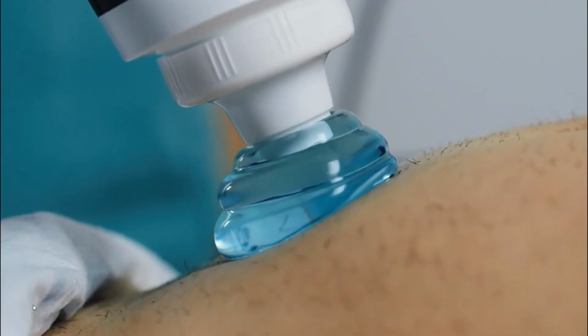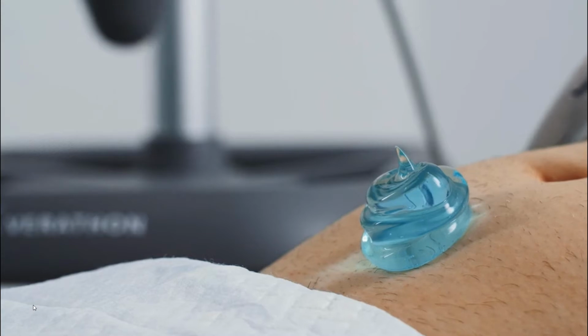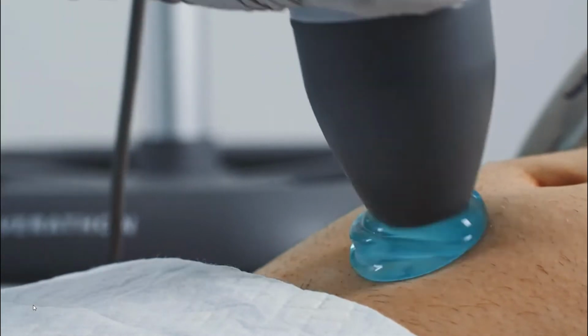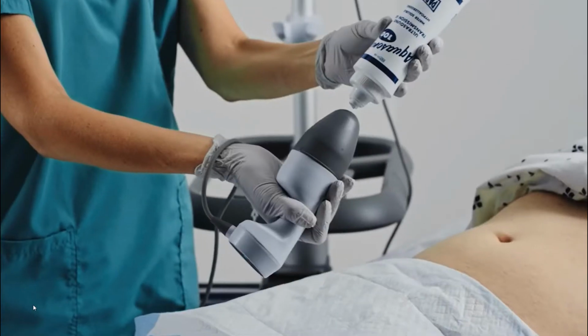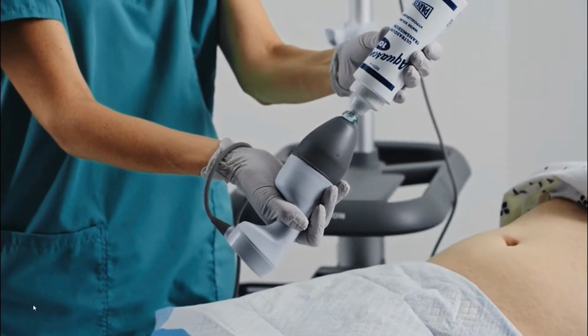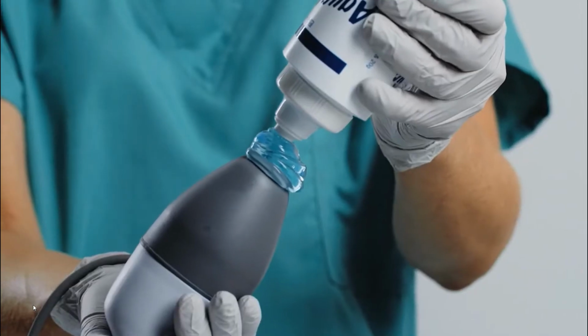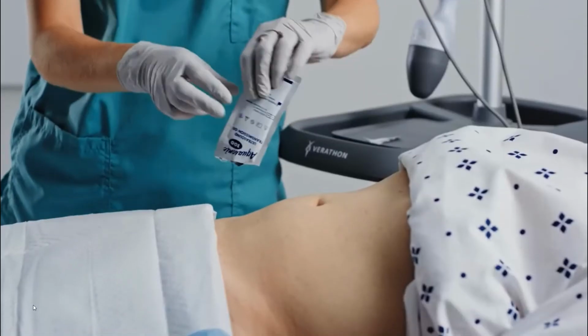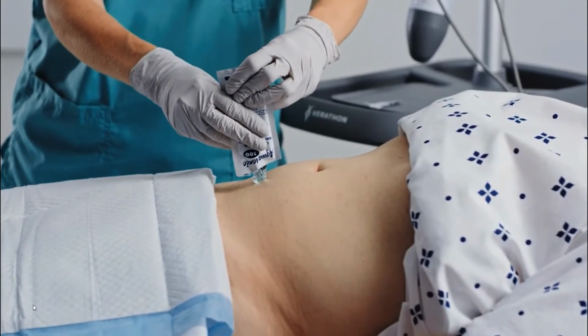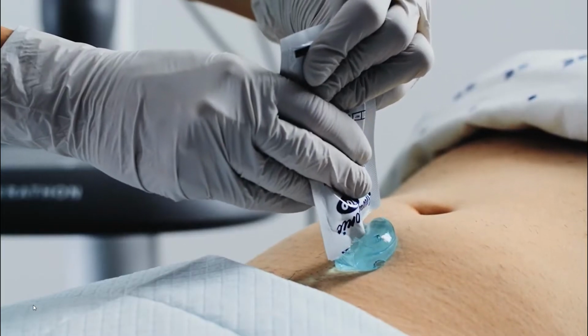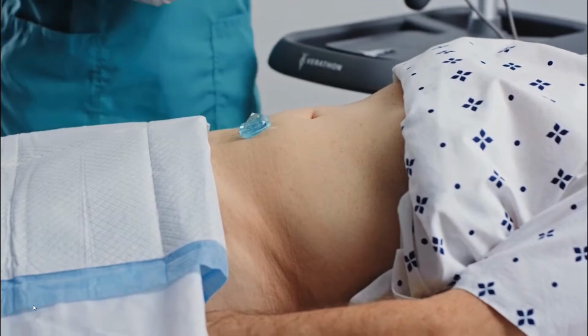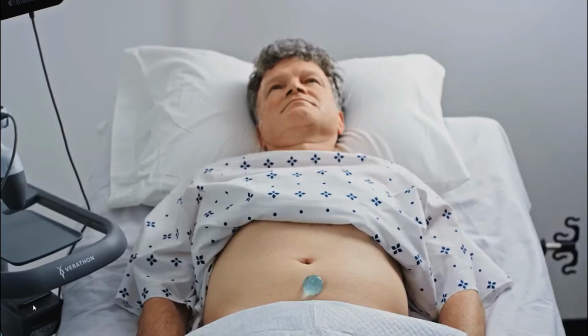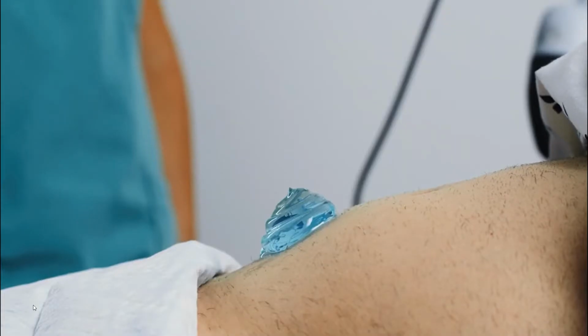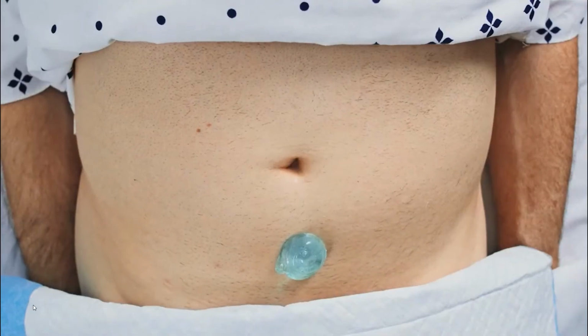Ultrasound waves have a difficult time traveling through air. With medical devices, a thick ultrasound gel is used to reduce air gaps between the patient's skin and the ultrasound probe. It is important to use an ample amount of gel between the skin and the probe tip. Apply gel to the probe tip or abdomen. A single-use 20-gram packet provides ample gel for use with most patients. After the gel is applied, you should have a thick mound on the abdominal target area, approximately the size and shape of a golf ball.